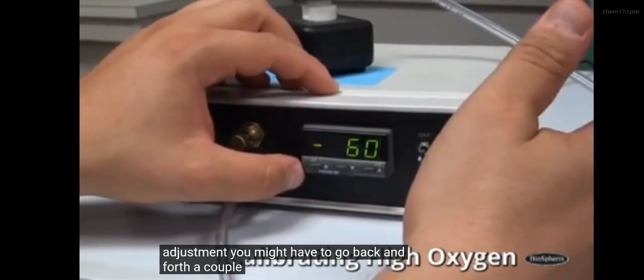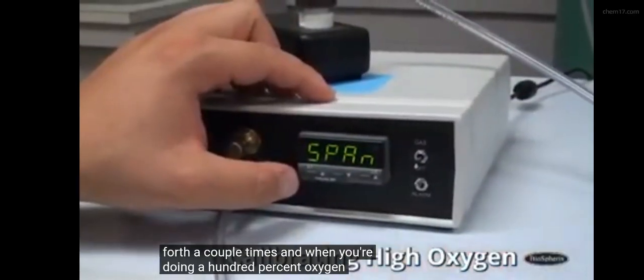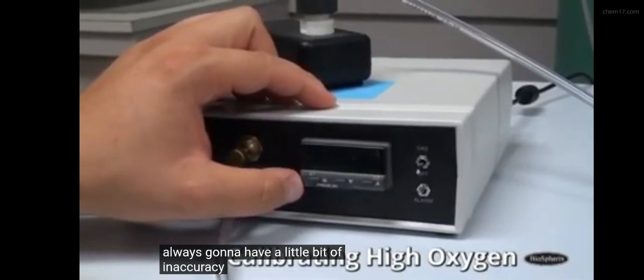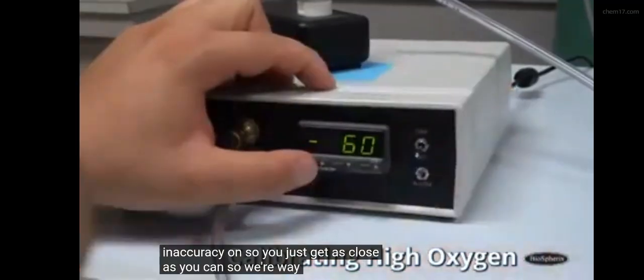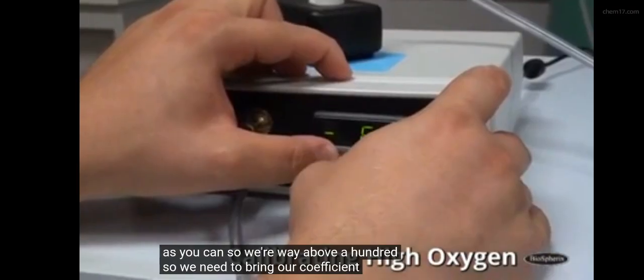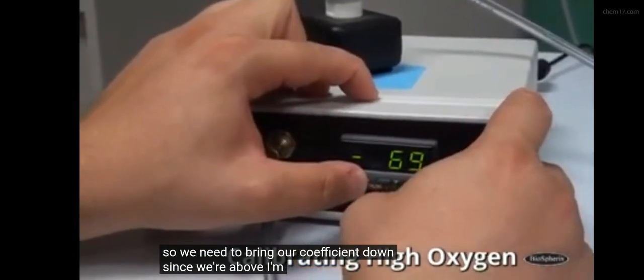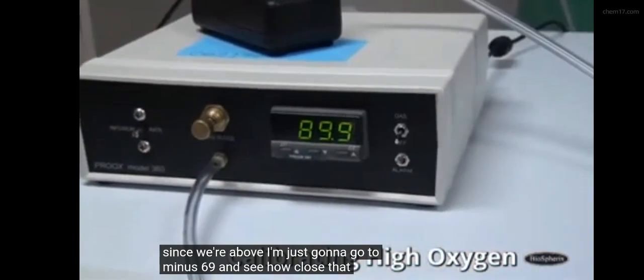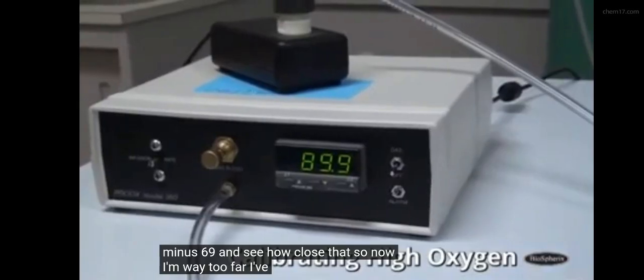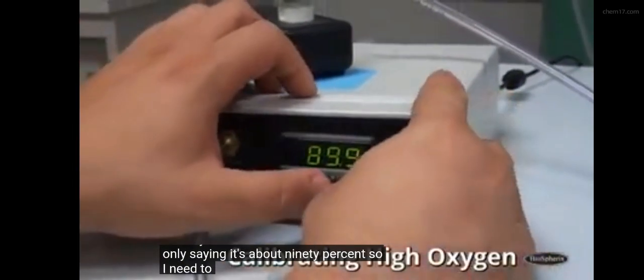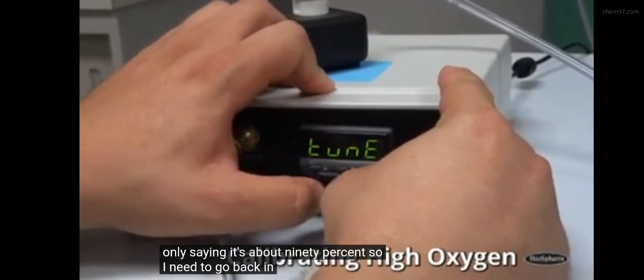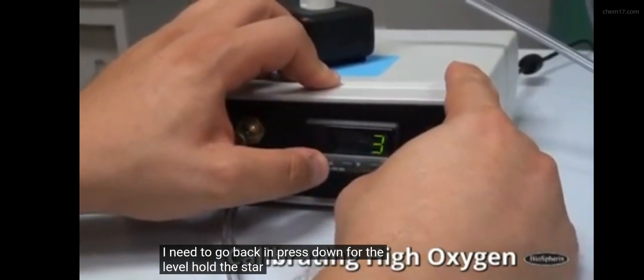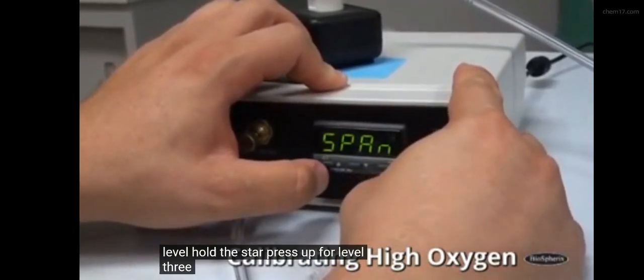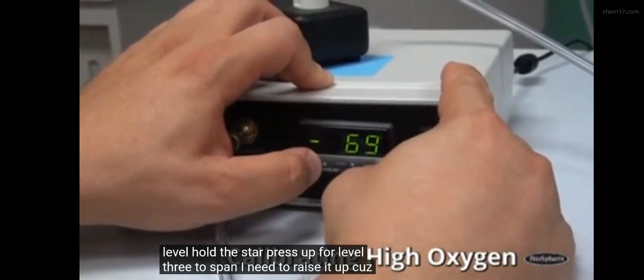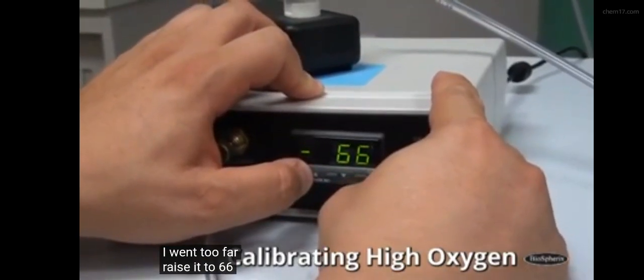Again, it's a coarse adjustment. You might have to go back and forth a couple times, and when you're doing 100% oxygen, it's always going to have a little bit of inaccuracy. So you just get as close as you can. We're way above 100, so we need to bring our coefficient down. Since we're above, I'm just going to go to minus 69 and see how close that gets us. So now I'm way too far. I've come back. Now it's only saying it's about 90%. So I need to go back in. Press down for level. Hold the star. Press up for level 3 to span. I need to raise it up because I went too far. Raise it to minus 66.